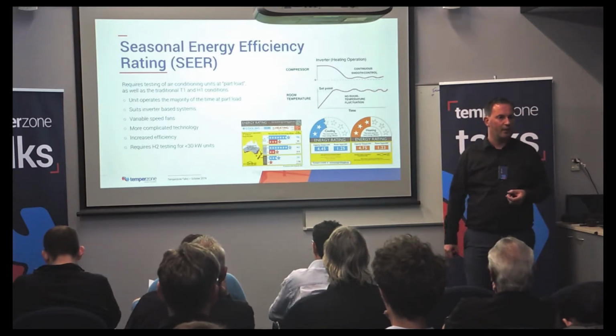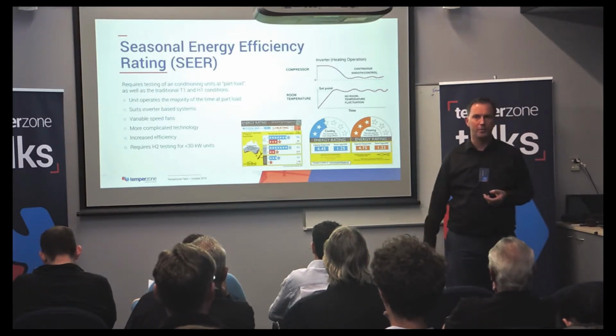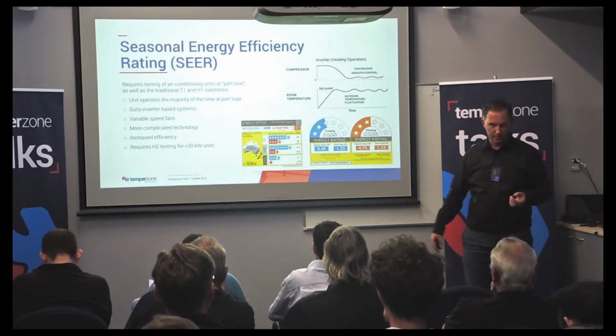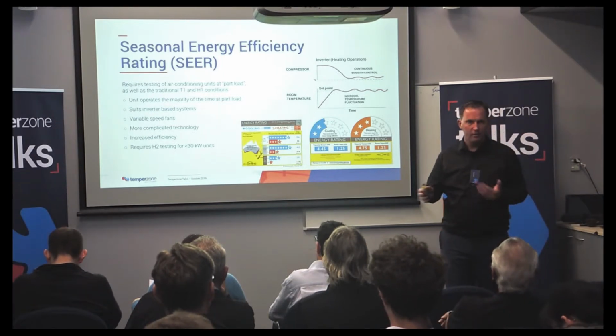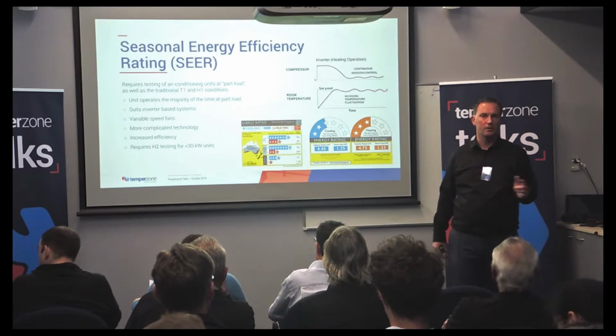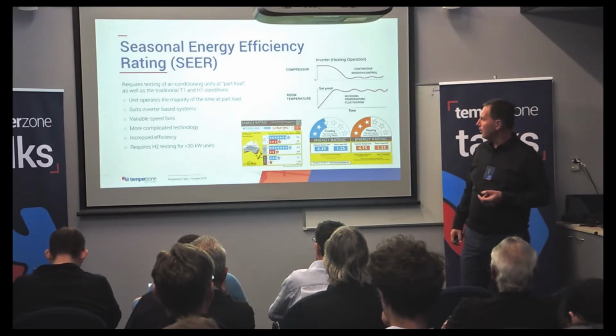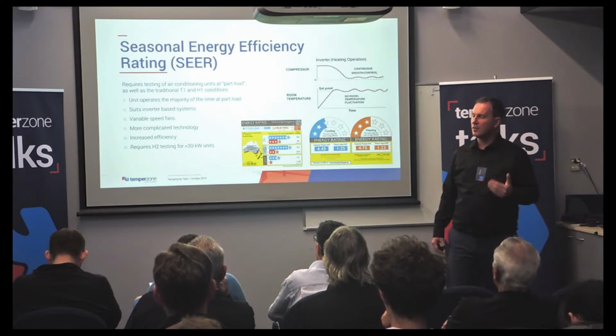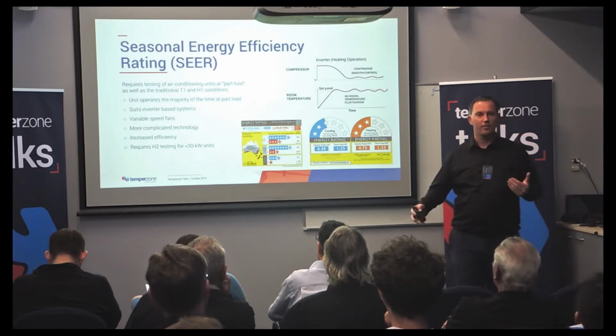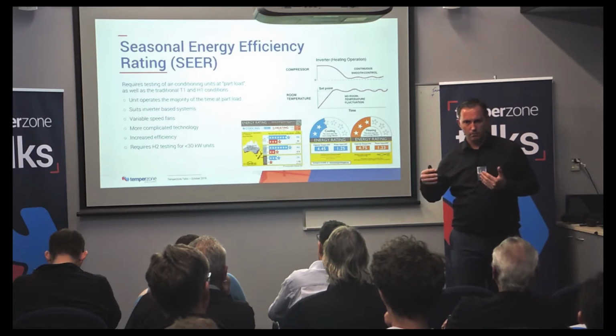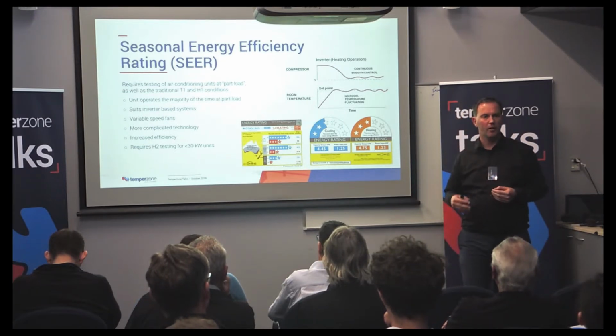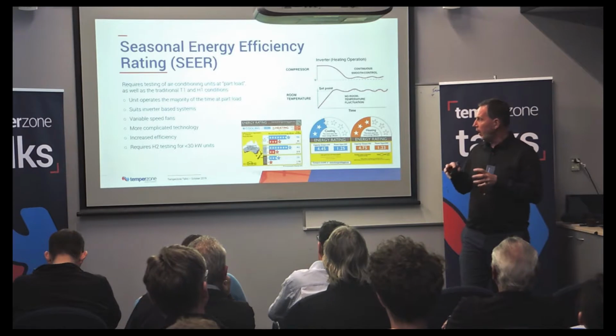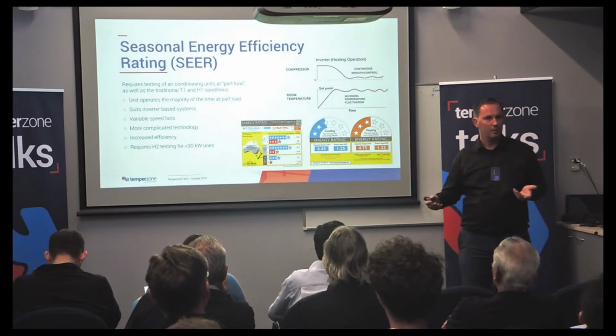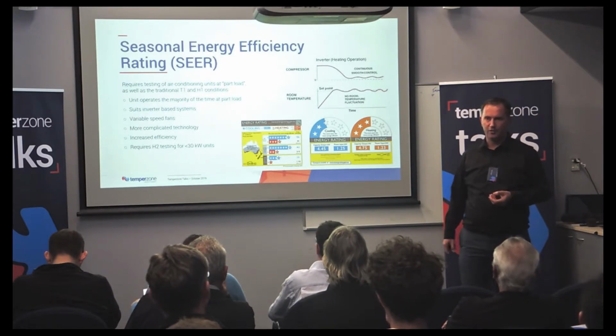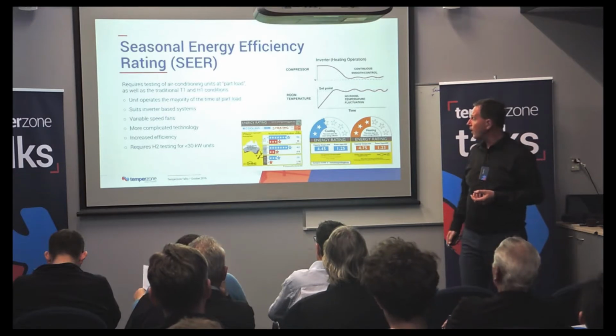And it very much drives us towards having variable capacity products: variable speed fans, variable speed compressors, and electronic expansion valves to adjust to the variable refrigerant mass flow going through the systems. The technology being used to do this is significantly more complicated than the electronics, but you get much better energy efficiency from doing so.